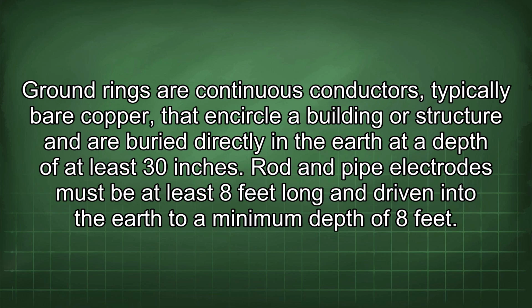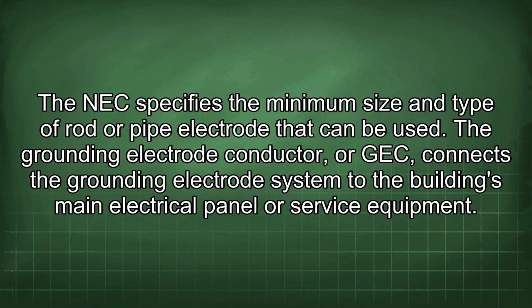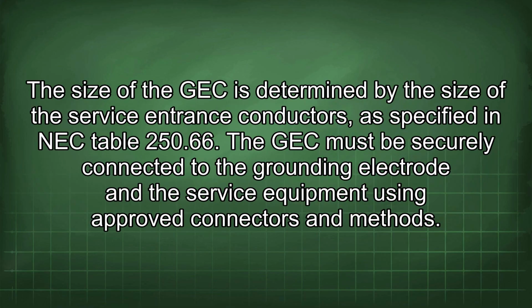Rod and pipe electrodes must be at least 8 feet long and driven into the earth to a minimum depth of 8 feet. The NEC specifies the minimum size and type of rod or pipe electrode that can be used. The grounding electrode conductor, or GEC, connects the grounding electrode system to the building's main electrical panel or service equipment. The size of the GEC is determined by the size of the service entrance conductors, as specified in NEC Table 250.66. The GEC must be securely connected to the grounding electrode and the service equipment using approved connectors and methods.